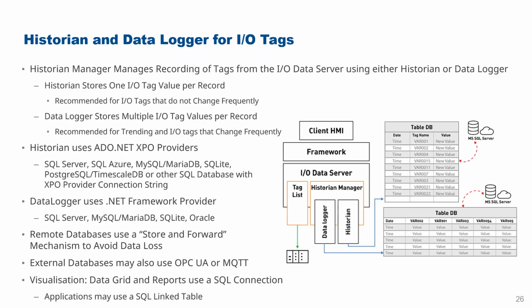Now what the data logger does is it stores multiple IO tags per record. So it's recommended for trends, it gives you better performance for trends, and also for time series type data and IO tags that change frequently, a data logger potentially gives you better performance. Inside Movicon, data loggers also give you better performance because of the way they work. So data loggers use a .NET framework provider, whereas a historian uses ADO.NET XPO providers. So the .NET framework provider potentially has higher performance, but we are depending on the .NET performance for this here.